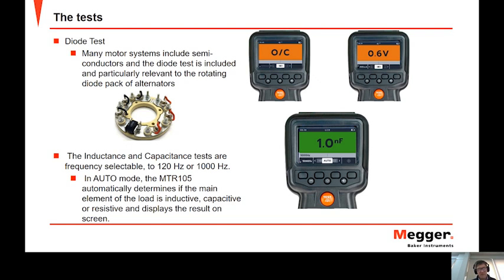We also have the diode test, and many motor systems include semiconductors, and the diode test is particularly relevant to the rotating diode pack of alternators. So we can check that the diode is functioning correctly. We have our LCR meter, where we can measure inductance and capacitance, and they are frequency selectable to 120 Hz or 1 kilohertz. We also have an auto mode for the LCR meter, and then the MTR will automatically determine if the load is inductive, capacitive, or resistive.